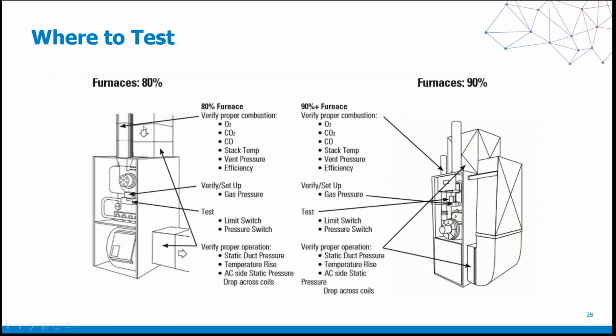80% furnaces, you can see here, right in here. We want to verify our draft and our efficiency and everything else right here. It's close, roughly, to the breech as we can, or 3 to 4 inches off of it, roughly. Some will have you go a little bit higher, but if you're within this sweet spot here, you're fine.